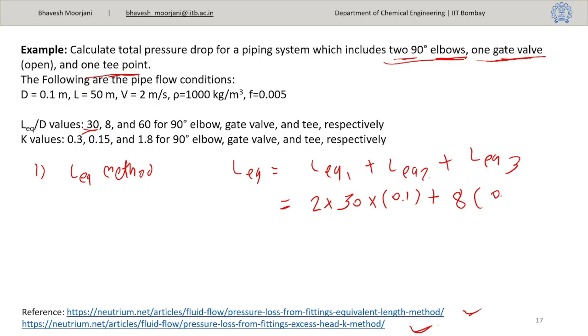So first computing through the L equivalent by D method, right? So L equivalent, what will it be? It will be L equivalent 1, which is due to the elbow, L equivalent 2, which will be due to the gate valve, and the equivalent length due to the T point, right? So we should get 3 equivalent lengths. We have two 90-degree elbows, so 2 times, for a 90-degree elbow the L by D value is 30, so 30 into the diameter, which is given as 0.1, plus for the gate valve the value is 8, 8 into 0.1, plus for the T point, 60 into 0.1, right?